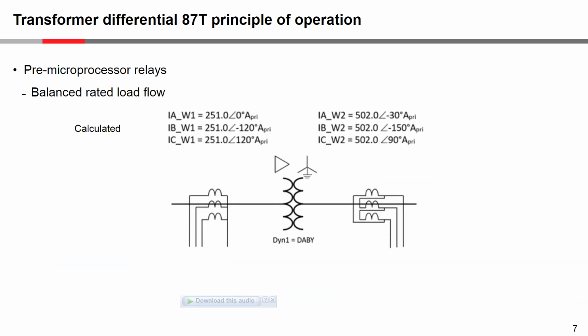So let's have a look then at a balanced load condition. Okay, so I just made a calculation with some transformer size, and so you can see the winding 1 currents, and because it's a transformer that is shifting the phase by 30 degrees, you'll see the currents flowing on the winding 2 side are then shifted by 30 degrees. So with the Y connection of the CTs on the delta side, you can see then that if you divide by the CT ratio such that you get the secondary currents, they will have the same phase as the primary currents, and hence they are really the phase reference side.